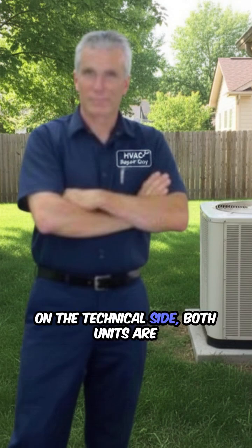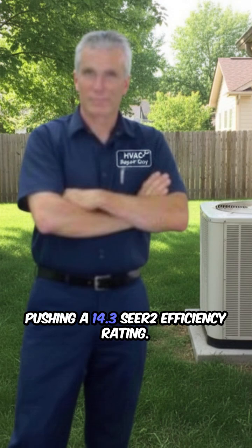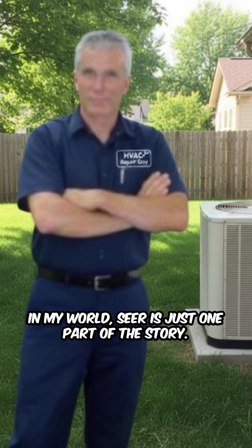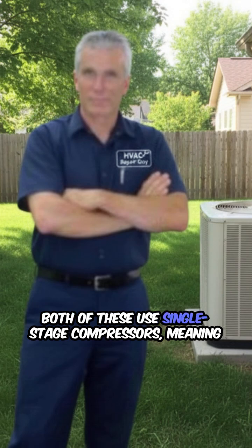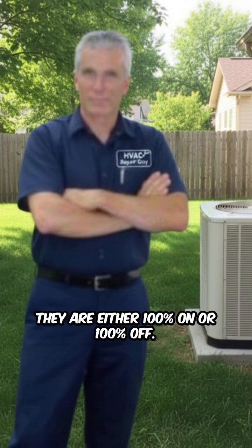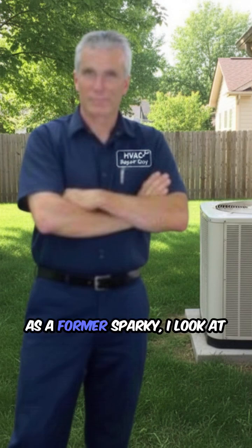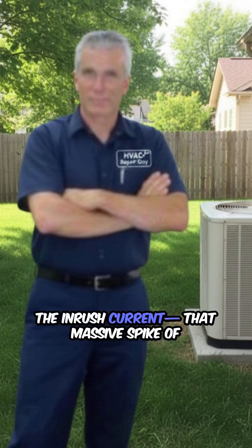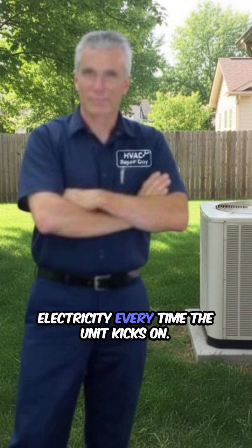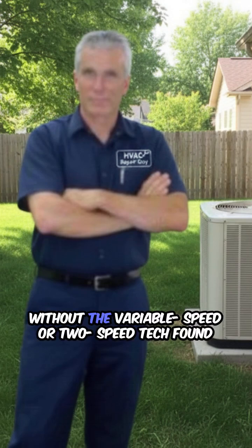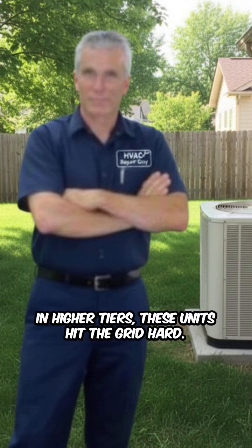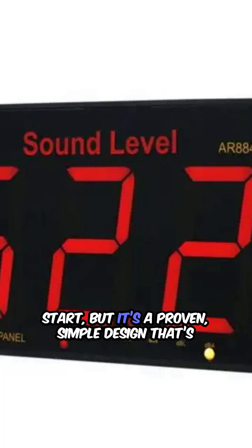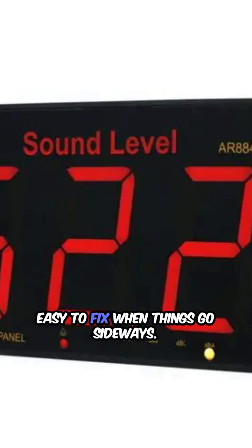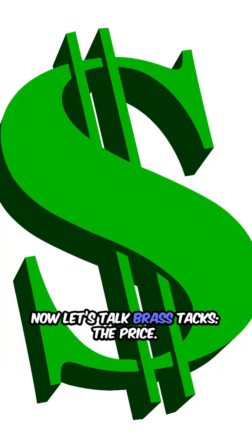On the technical side, both units are pushing a 14.3 SEER 2 efficiency rating. In my world, SEER is just one part of the story. Both of these use single-stage compressors, meaning they are either 100% on or 100% off. As a former Sparky, I look at the inrush current, that massive spike of electricity every time the unit kicks on. Without the variable speed or two-speed tech found in higher tiers, these units hit the grid hard. You're going to hear that thump when they start, but it's a proven, simple design that's easy to fix when things go sideways.